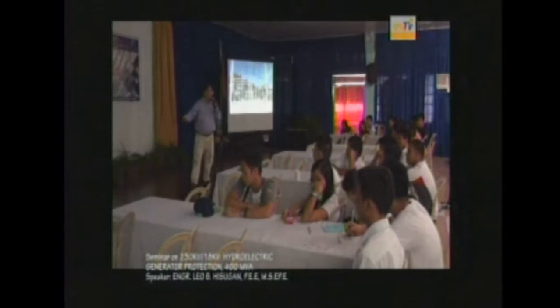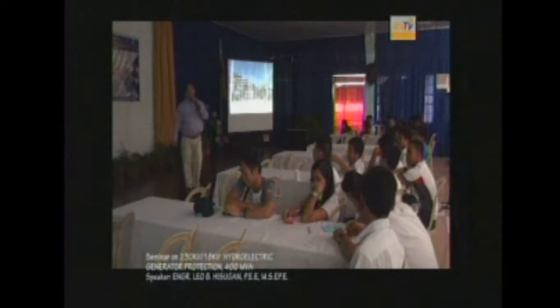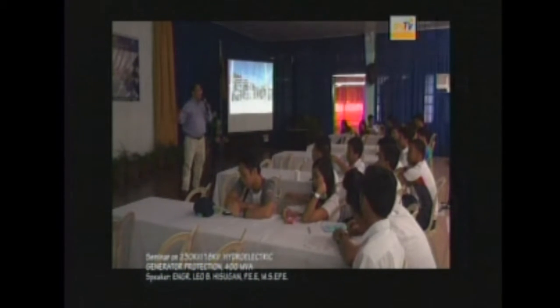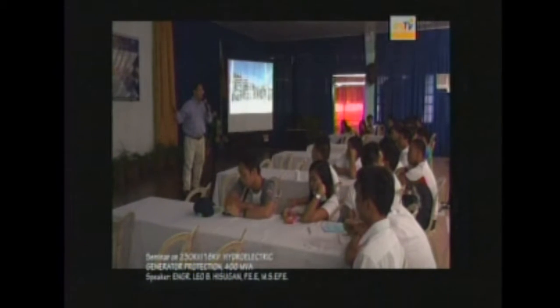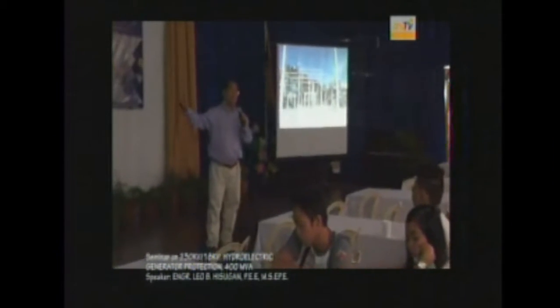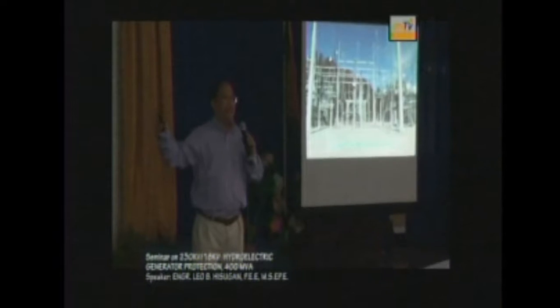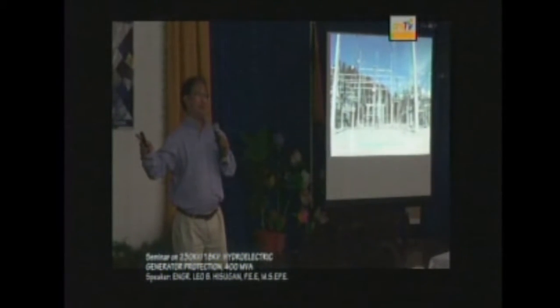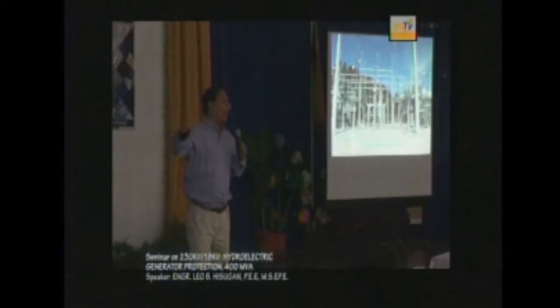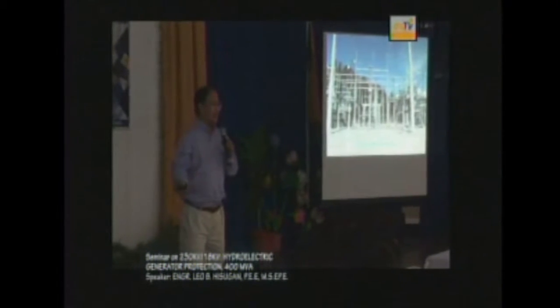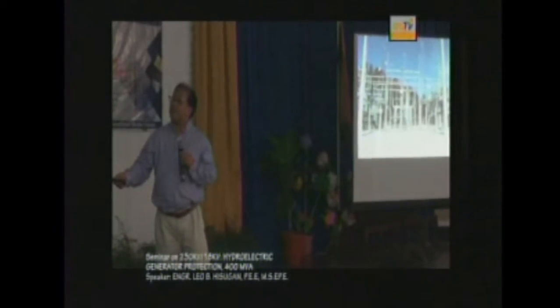The circuit breaker, right? Okay. Yeah, the voltage is 230 kV, and normally the continuous current capacity is like 2,000 amps, for example. And the short circuit current capacity is 63,000 amperes. So it can interrupt current at 63,000 amps, while the continuous current capability is 2,000 amps. Steady state, you can open and close your breaker at 2,000 amps. So the CCVT is your potential transformer, and this potential transformer is the one feeding your meters and your protective relays. So we're using 67 volts line to neutral for the relays and 120 volts for the meters.